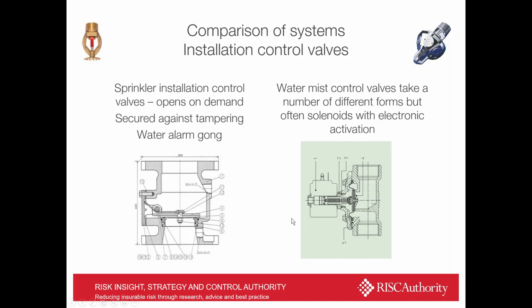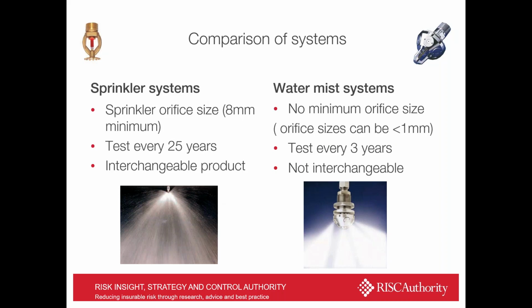And when you look at the hardware that's used as well, I mentioned Victorian architecture on the left-hand side. That's a cutaway of a sprinkler control valve, a large flap that lifts away, generally revealing a hole around 4 inches in size for the water to get through. But water mist systems require much lower quantities of water, but depend on much smaller orifice type equipment, such as solenoid valves, which have a much higher failure rate than sprinkler alarm valves.